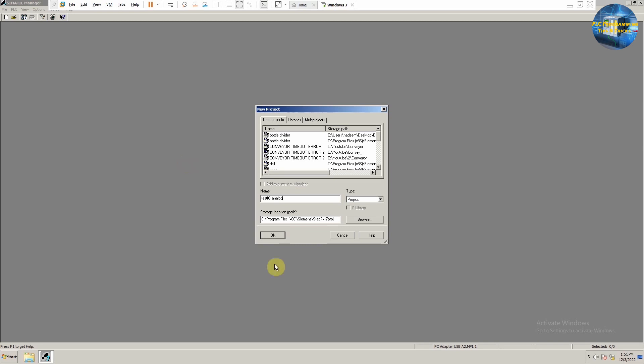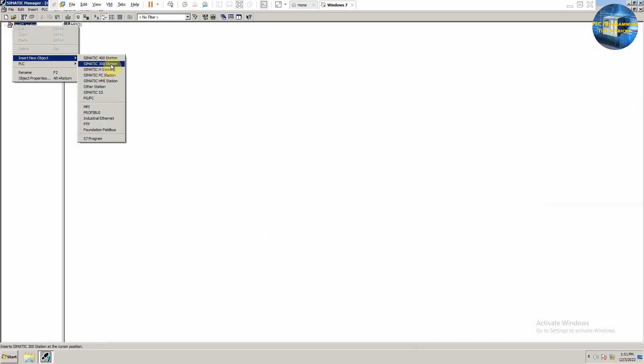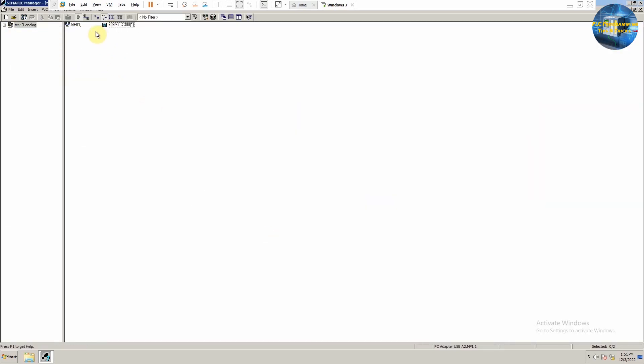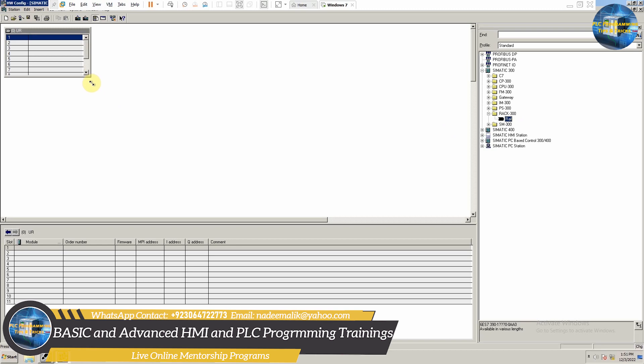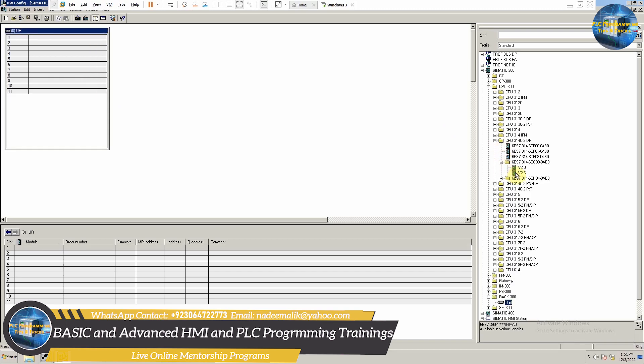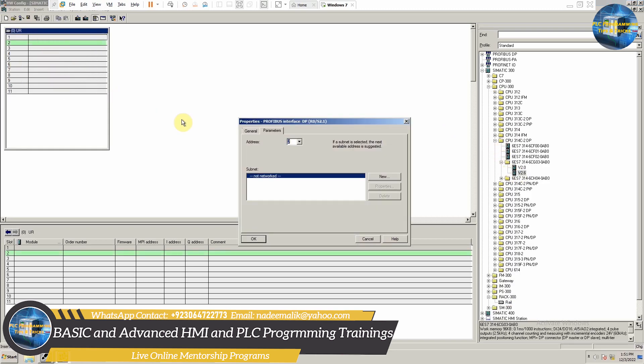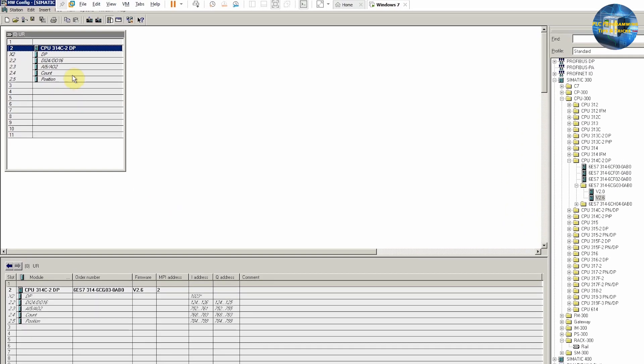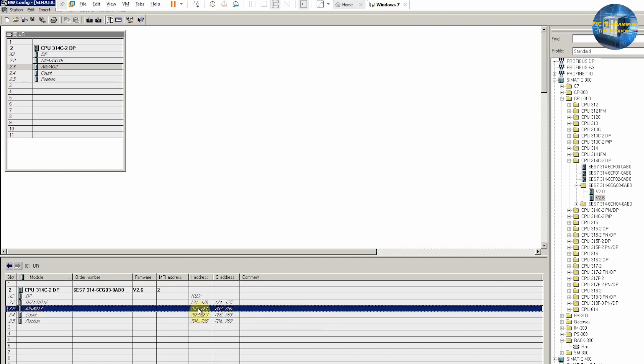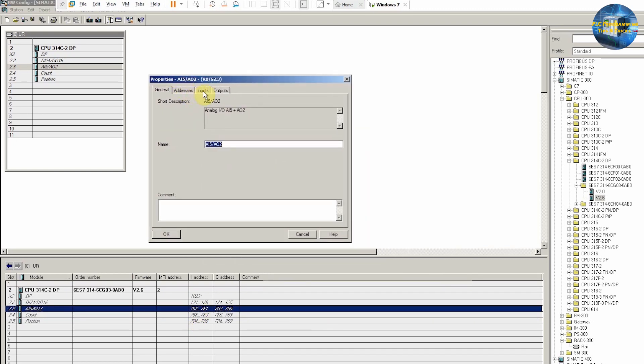Next we will go to the SIMATIC Manager software and create a new project. We will insert a new S7-300 station, open it by double-clicking, and open the hardware configuration. First we will insert a rail for this PLC station, then insert a 314C-2 DP PLC version 2.6 onto this rail. No need to configure the network for this project — just click OK to proceed. You can now see the analog and digital inputs and outputs of this PLC.